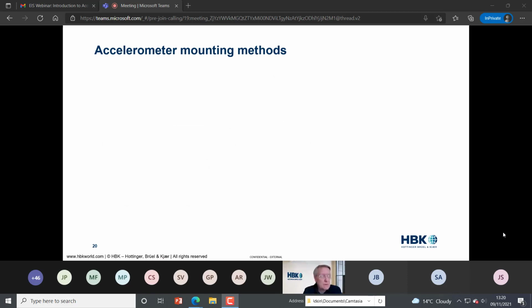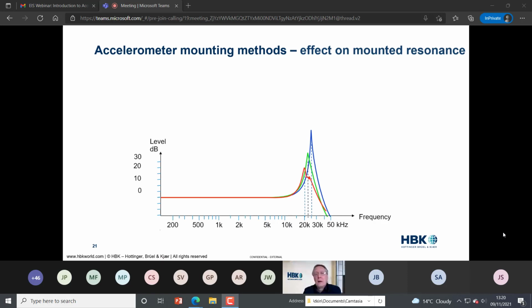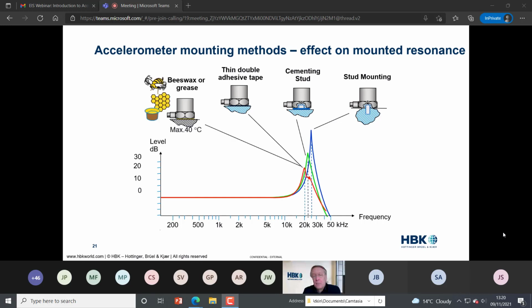Okay, I've been talking about the mounted resonant frequency of an accelerometer. That is how the accelerometer will perform with an ideal connection between the accelerometer base and the surface that you wish to measure the vibration on. Now, the type of mounting method that you choose will determine where the effective resonance is of your accelerometer. So it's not possible just to read the resonant frequency off the calibration chart and automatically assume that that is what your system will be measuring when you connect the accelerometer to a surface.